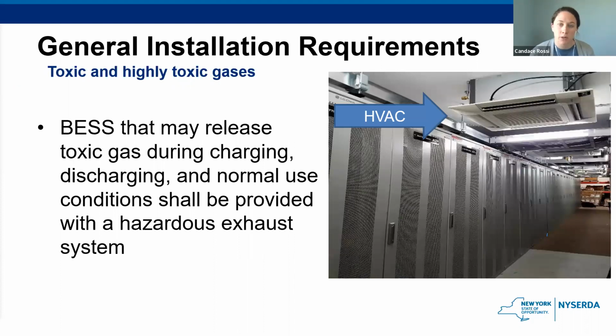The next general requirement we have is for toxic and highly toxic gases. Systems that are installed indoors and have the potential to release toxic and highly toxic gas during normal use will be required to have a hazardous exhaust system.